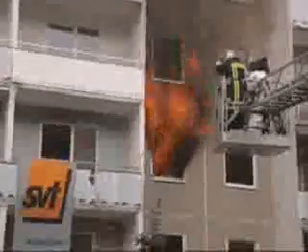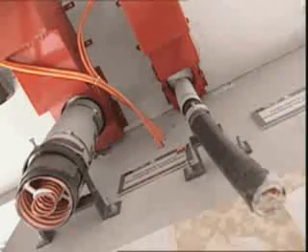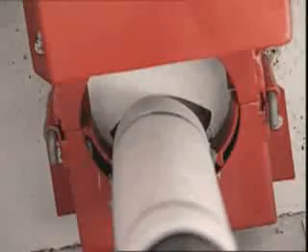The testing room shows a real inferno. On the outside, the flames are reaching out of the window and up over the next level. In the level below the test room, the plastic distancers are meanwhile dropping fire. The spread of fire to a lower level now becomes clearly visible. The broadcasting cables protected by the PYRO-SAFE power cut system do not show any effect. The system has long since cut the cable and closed the cross-section with the blade.